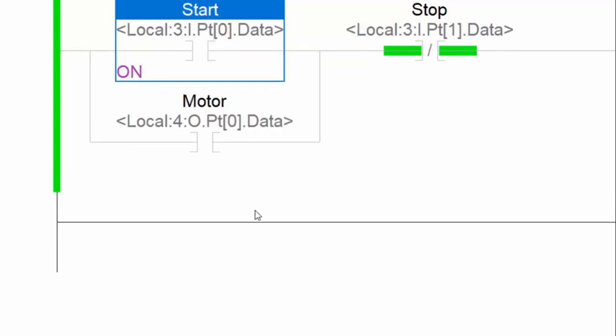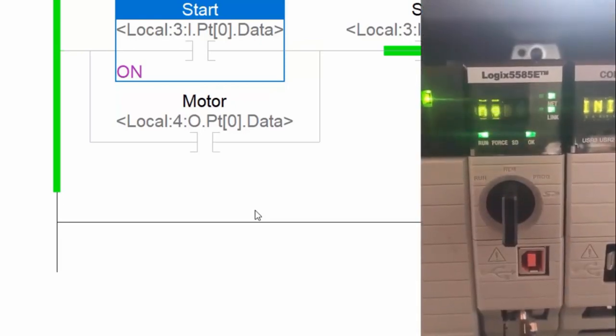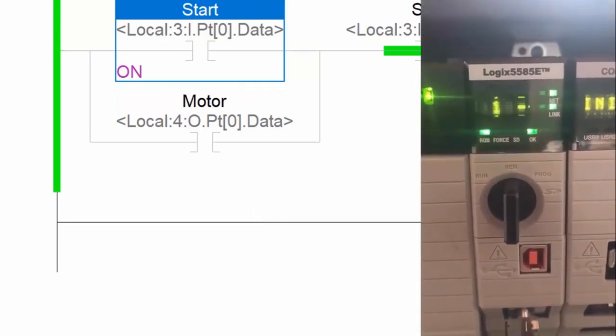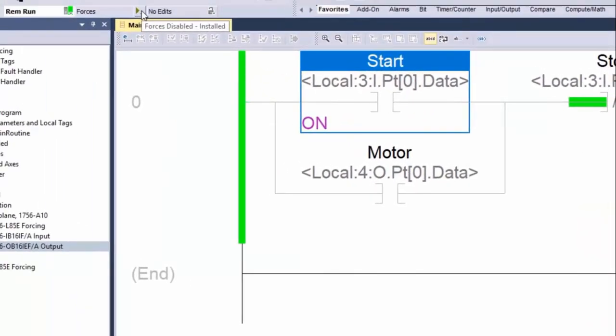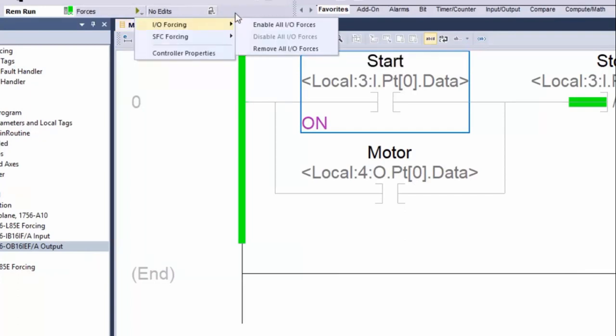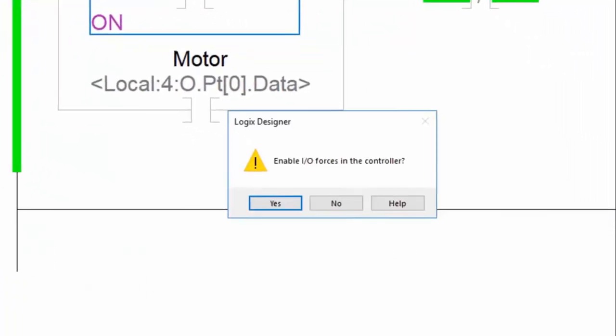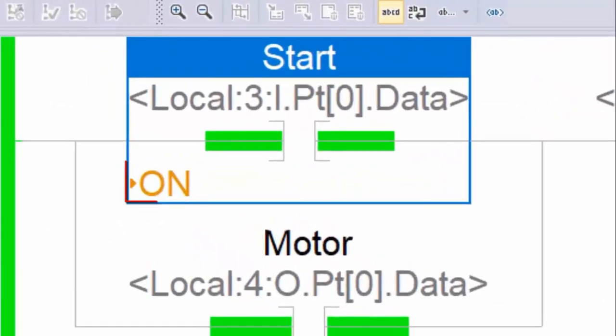We can see from the status LED of the controller that a force is set, but it is not active yet. The force LED light is now flashing. The last step is to enable the force. Go back to the force menu and under IO forcing, select enable all IO forces. To activate the force, click yes.